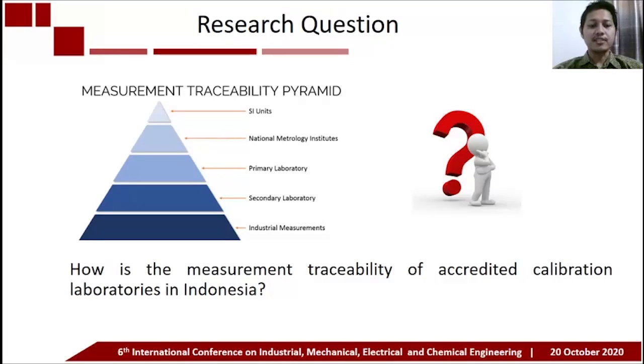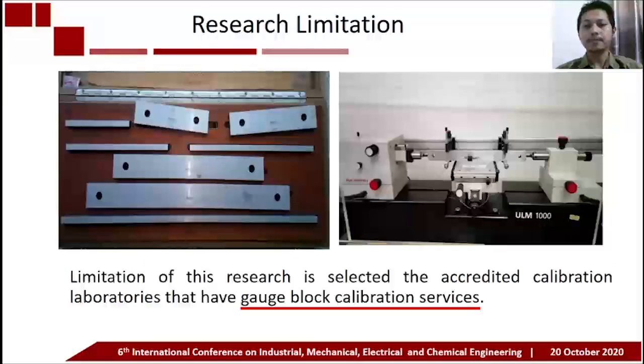Our question in this research is: how is the measurement traceability of accredited calibration laboratories in Indonesia? In calibration activity, metrological traceability is the most fundamental and indispensable element. According to clause 6.5 of the ISO/IEC 17025 standard, metrological traceability is obtained from calibration activities against standards or measuring instruments with a competent calibration laboratory. The limitation of this research is that we selected accredited calibration laboratories that have gauge block calibration services.